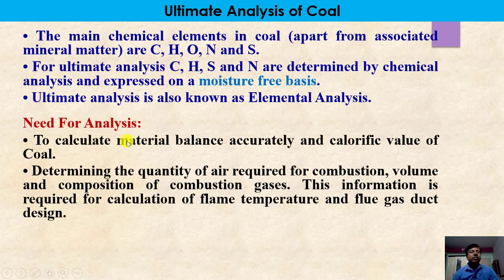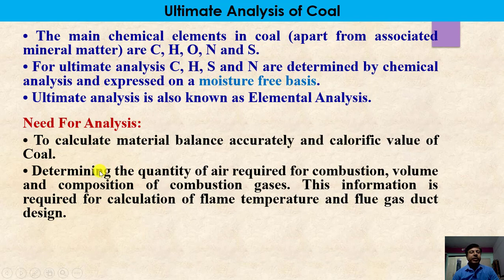The importance of ultimate analysis: it is required to calculate material balance accurately and to determine the calorific value of coal. It is also used for the combustion of coal — determining the quantity of air required, volume and composition of combustion gases. This information is required for calculation of flame temperature and flue gas duct design.